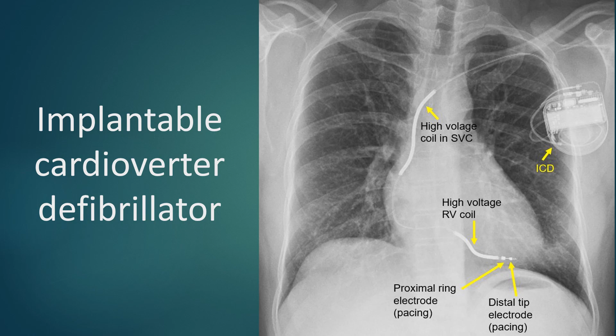One high voltage coil is in the superior vena cava, while another one is seen in the right ventricle. 2 pacing electrodes are seen beyond the high voltage coil in the right ventricle. This is a single chamber ICD. A dual chamber ICD will have an additional atrial lead which is useful in sensing atrial arrhythmias and avoiding inappropriate shocks. Inappropriate shocks are an important disadvantage of the ICD.